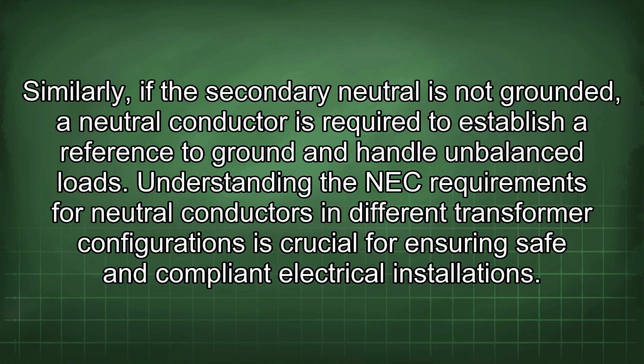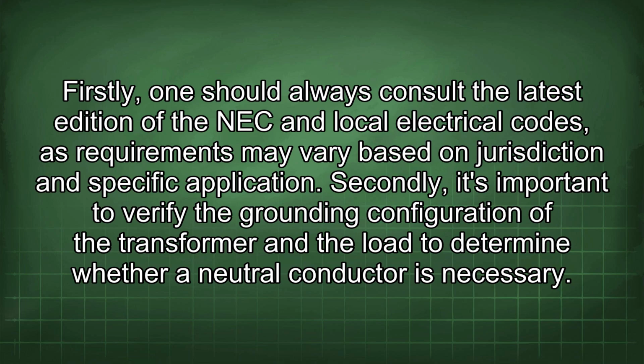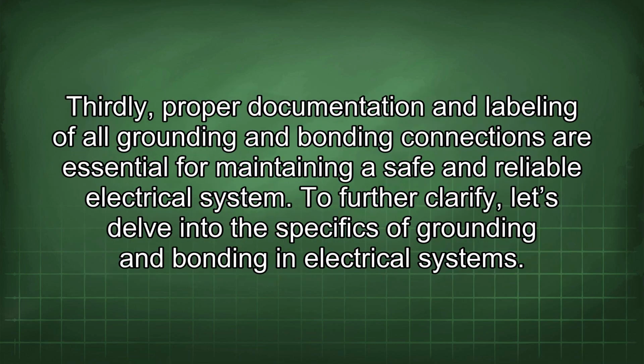compliant electrical installations. Firstly, one should always consult the latest edition of the NEC and local electrical codes, as requirements may vary based on jurisdiction and specific application. Secondly, it's important to verify the grounding configuration of the transformer and the load to determine whether a neutral conductor is necessary. Thirdly, proper documentation and labeling of all grounding and bonding connections are essential for maintaining a safe and reliable electrical system. To further clarify, let's delve into the specifics of grounding and bonding in electrical systems.